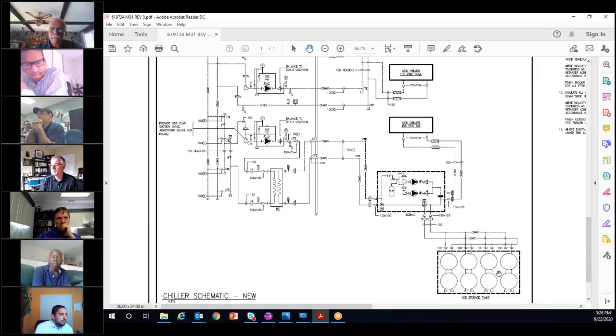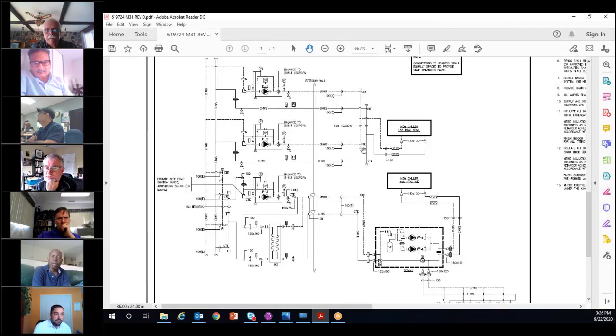So this kind of design concept was chosen for a few reasons. One, it maintained at least the 300 or so tons of capacity for the hospital, which we realized after a load profile analysis really dropped off to about half of that at night, even on a warm Sudbury summer day. So that's why we have 1 chiller up here, which remained on the existing water loop, which could provide cooling at any given time.